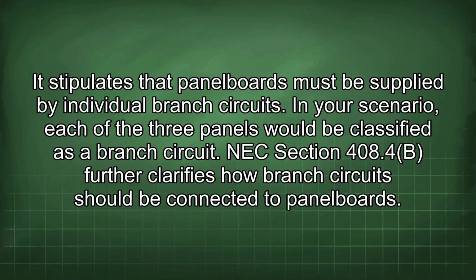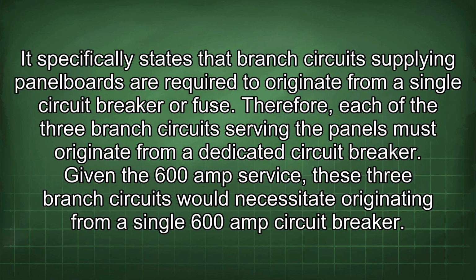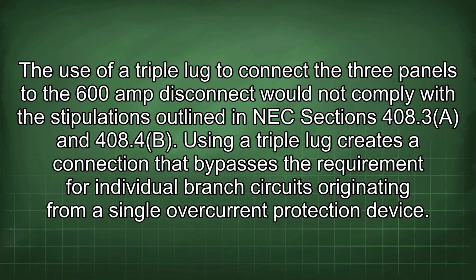NEC Section 408.4(B) further clarifies how branch circuits should be connected to panel boards. It specifically states that branch circuits supplying panel boards are required to originate from a single circuit breaker or fuse. Therefore, each of the 3 branch circuits serving the panels must originate from a dedicated circuit breaker. Given the 600 amp service, these 3 branch circuits would necessitate originating from a single 600 amp circuit breaker. The use of a triple lug to connect the 3 panels to the 600 amp disconnect would not comply with the stipulations outlined in NEC Sections 408.3(A) and 408.4(B).